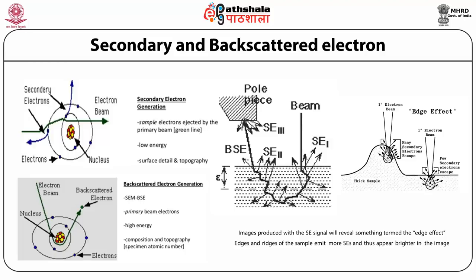Backscattered electrons are those electrons scattered backward and emitted out of the specimen — sometimes called reflected electrons. Since backscattered electrons possess higher energy than secondary electrons, information from relatively deep regions is contained in them. Backscattered electrons are sensitive to the composition of the sample: when the atomic number of constituent atoms is larger, the backscattered electron yield is larger, meaning areas with heavier atoms appear brighter in the backscattered electron image. This image is therefore suitable for observing compositional differences. Secondary electrons are generated by three different mechanisms: SE1, SE2, and SE3.